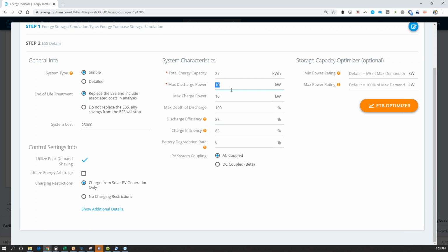And so in this kind of equivalent example, we would be assuming that, for the same amount of storage, we would be wanting a 30 kilowatt inverter, and that it might actually be surging up to 50 kW for that time frame. So what we're basically buying is an inverter that can surge up to 50 kilowatts.